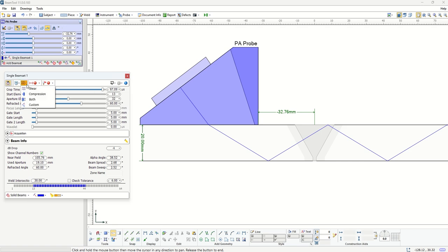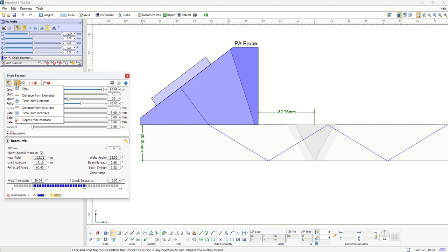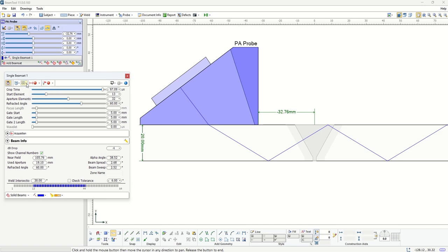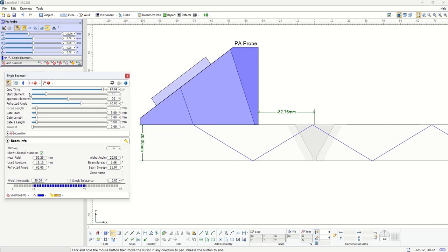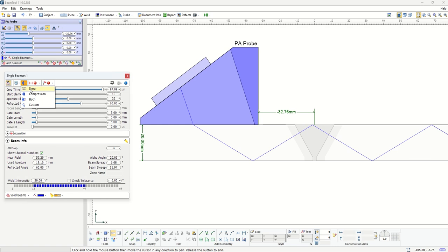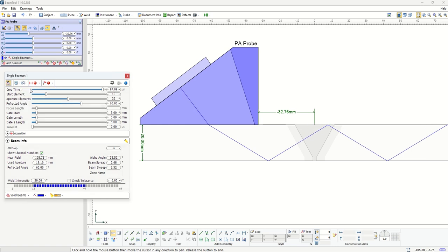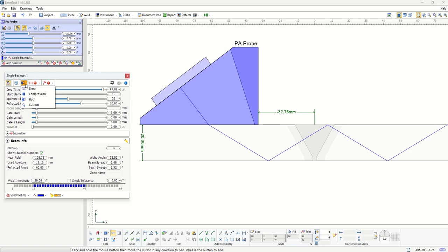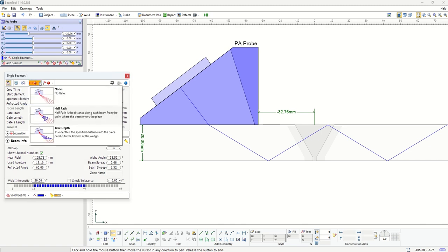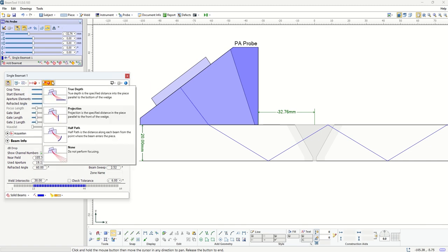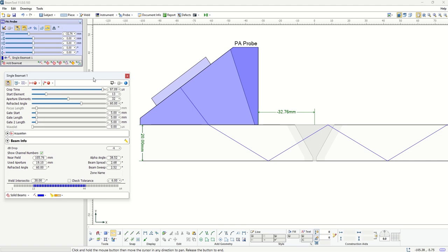We can choose what type of beam mode we are using. In this case we're using shear. If you use compression, you realize that the beam that is generated is now going to be a compression wave. We have options in terms of gate and focus that we can show you in upcoming examples.